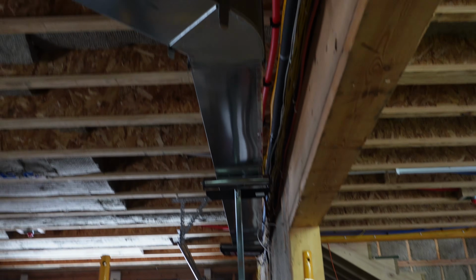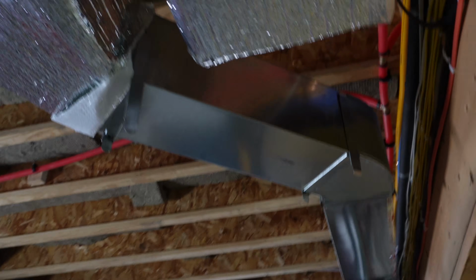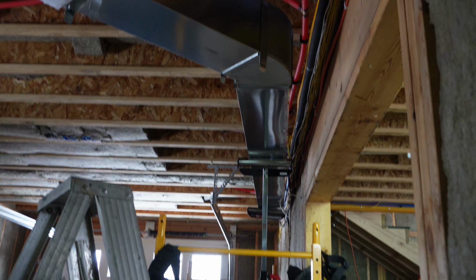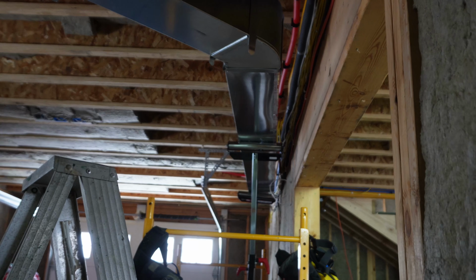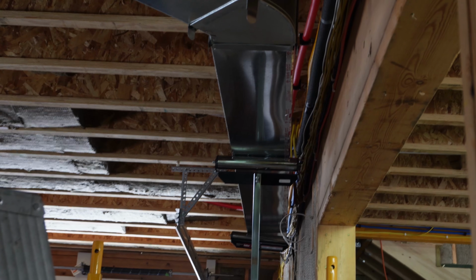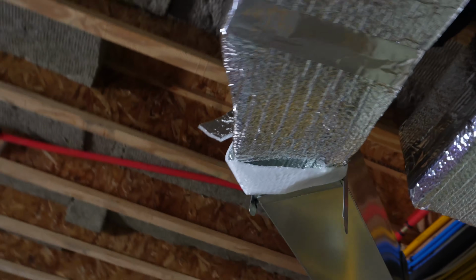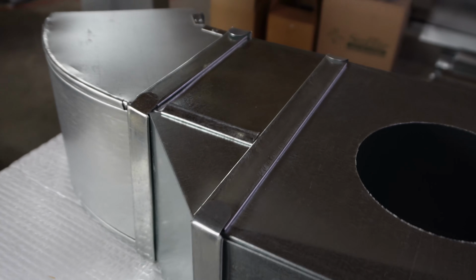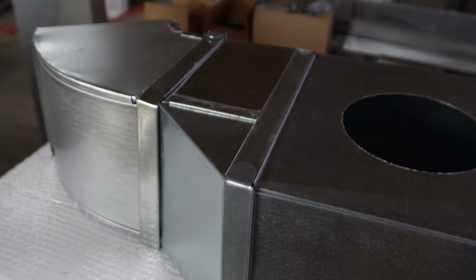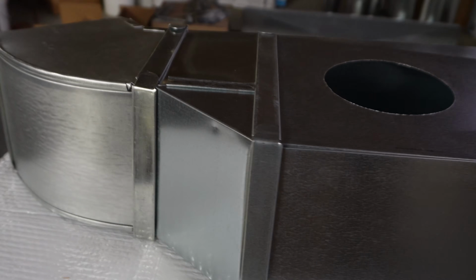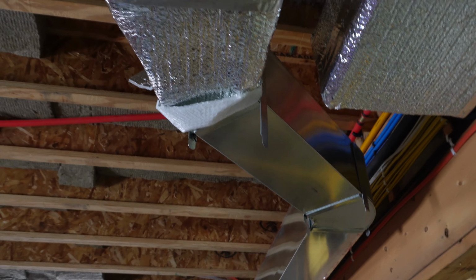In theory, these two 45-degree rectangular elbows should make this a perfect parallel run. If the one is parallel, the second run should be parallel, and it's clearly not. Digging into it, I think my issue is actually when I put this little reducer and this 45-degree elbow together, somehow the angle became just tighter than 45 degrees. I'm really not sure how, but we're gonna have to compensate for it now.